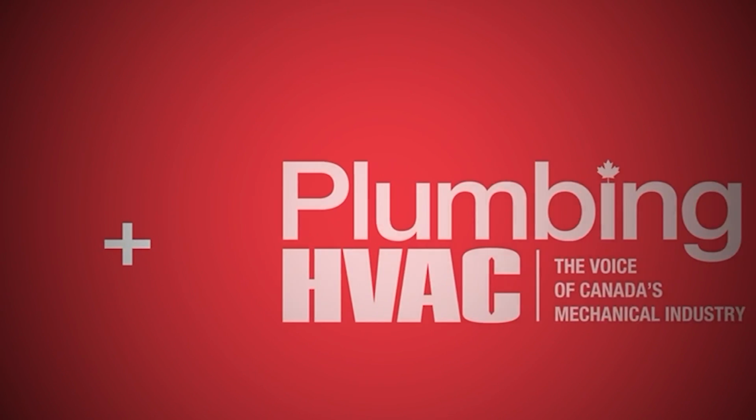Okay. So looking at this unit from the flowing of water going from the outdoor unit to the indoor unit, at 80,000 BTUs, I'd expect 7 to 9 gallons a minute. Is this kind of the same? There's no special flow rules involved here? No, there's some special flow rules, but you pretty much nailed it. Okay. So if you're at 8.5 GPM, you're in good shape. Yeah. Like we talked about on the air handler, the contractor has to be cognizant of how much loop they've put in the hydronic line, where the bends are. Yeah. What type of material you're using? Understand ID versus OD. Yeah. Common sense stuff.